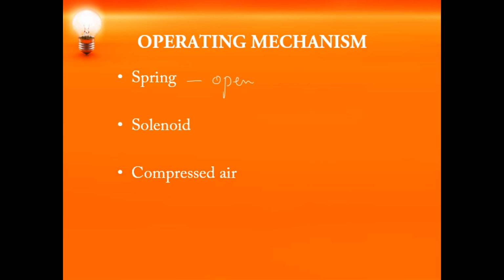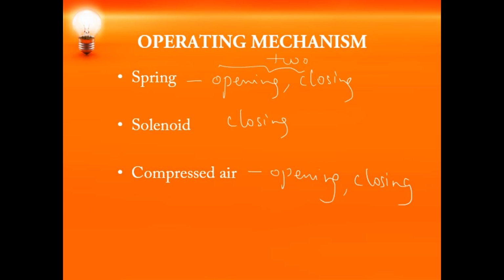For opening we go either for spring or for compressed air, that is to open the contacts of the circuit breaker. Whereas for closing, you can go for the spring, the solenoid, or compressed air. So opening and closing both can be achieved by spring and compressed air, but solenoid is mainly used for closing operation. And when we use spring for both opening as well as closing, we need to have two separate springs, one which is used for closing and one which is used for opening. And always the closing spring will have a higher energy level compared to opening. Clear? The closing spring should have a higher energy level compared to the opening, and it will usually be operated by motor driven gears.